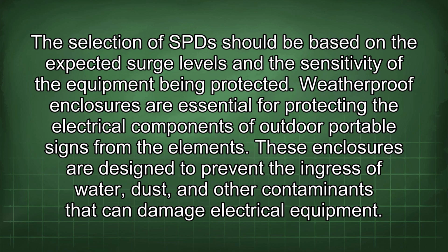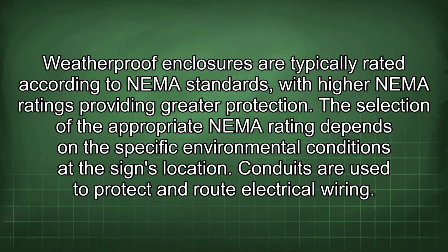Weatherproof enclosures are essential for protecting the electrical components of outdoor portable signs from the elements. These enclosures are designed to prevent the ingress of water, dust, and other contaminants that can damage electrical equipment. Weatherproof enclosures are typically rated according to NEMA standards, with higher NEMA ratings providing greater protection. The selection of the appropriate NEMA rating depends on the specific environmental conditions at the sign's location.